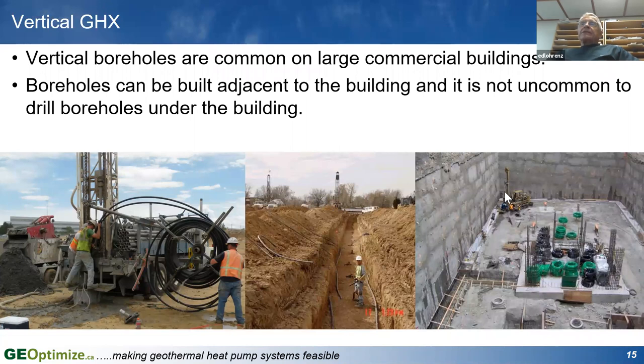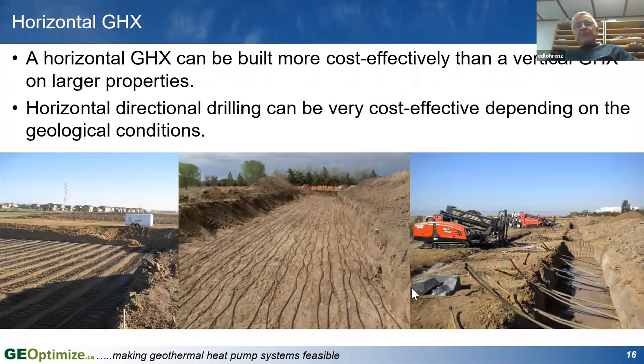You're looking at piping being installed under a building. This is in Vancouver. This is in a place where you've got a lot more space to play with. Horizontal loops, if you've got space to install the pipes in the ground, excavating a trench 5 or 6 or 7 feet deep, or drilling horizontally down to 15 or 20 or 30 feet deep, can be a more cost-effective way to install pipe in the ground. Simply, it's just cheaper to build that in a lot of cases.